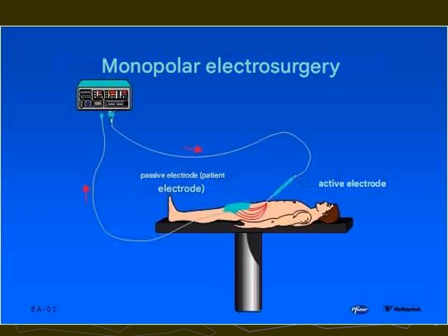Well, here we also show electrosurgery. I will raise the active electrode. We have a high current density. What we see here is a passive electrode with a fairly large area. Under it, of course, there will be much less effect; dissection occurs only under the active electrode.